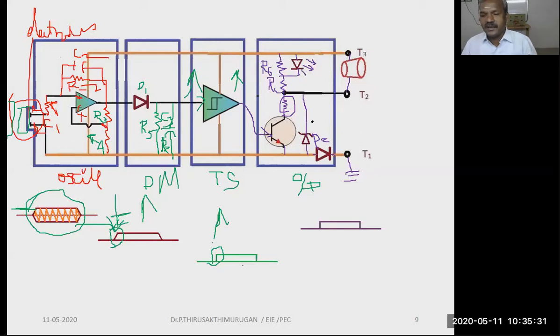But these devices: this LED is for indication. This RTD is for protection. This Zener diode is for regulation. This is also a protective diode. The other things are similar to your inductive proximity pickup switch. The major difference between this and that is that this can detect any material having a high dielectric value. If the dielectric constant is more than 1.2, detection is very easy. Whereas the inductive proximity sensor mostly detects ferrous materials, iron-type materials, conducting materials.